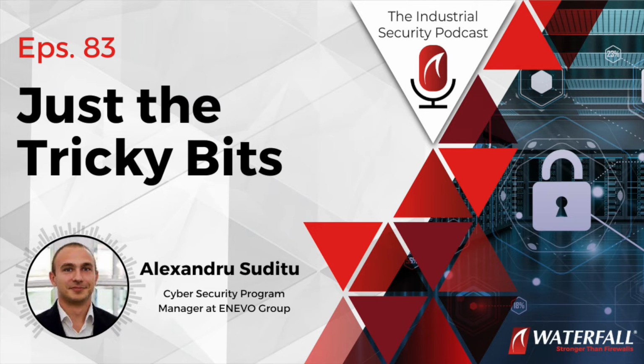The issue is that most cybersecurity companies usually come with an IT mentality. Not that an IT mentality is necessarily the issue, but you need to touch it from both sides: you have the cybersecurity expertise of what needs to actually be hardened, but you also need to cover it from the engineering side, making sure every change you're doing doesn't impact the process being governed.